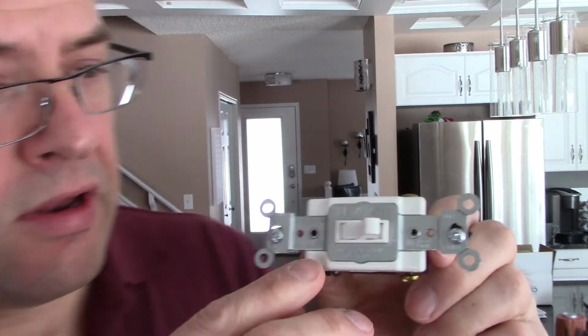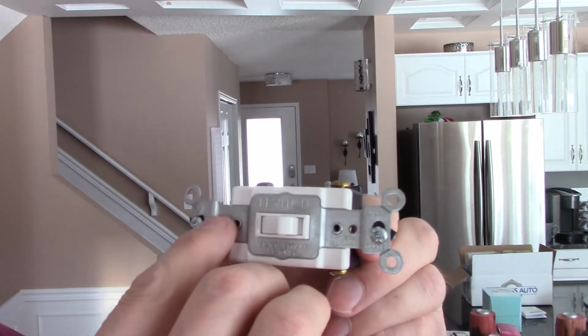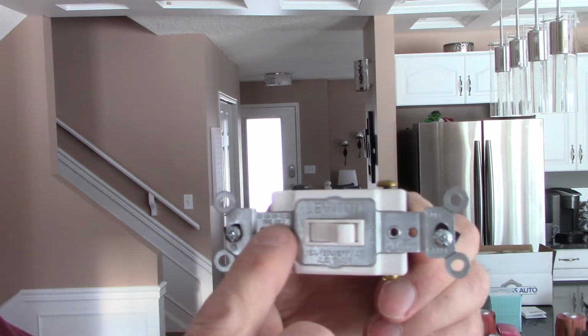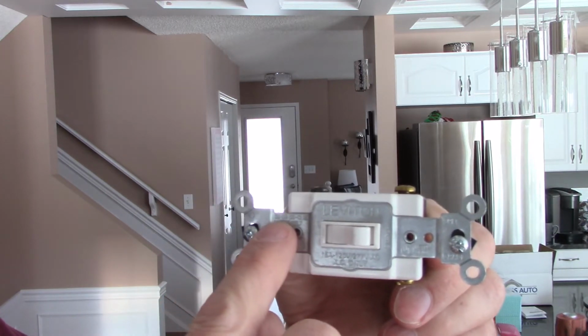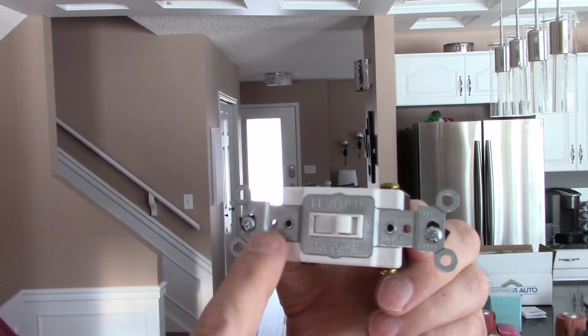The other part of it is that if you have aluminum wiring or if you have copper wiring, that matters to the switch. If you have aluminum wiring, as you can see on this switch again, right in here, copper or copper-clad wire only. CU means copper. This switch is not made for aluminum use.